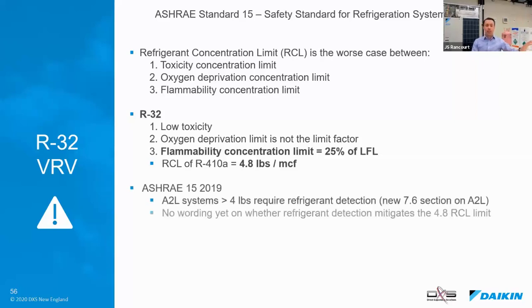So ASHRAE 15 says, all right, to put A2L in the building, you need refrigerant detection if you're over 4 pounds, which all these systems will be. But there's no wording yet on the RCL. So if I've got refrigerant detection, does that mean that I don't need to meet the 4.8 pounds? Because if I do, that becomes very challenging. So that's still left to be done.